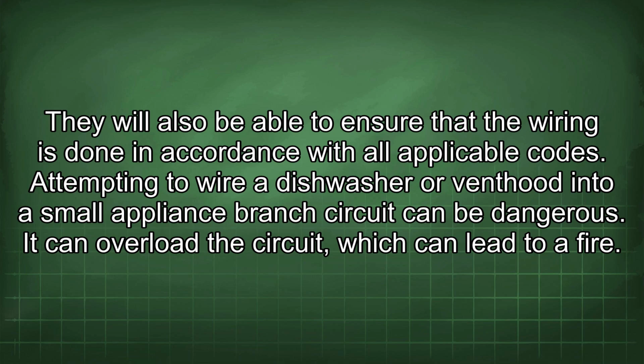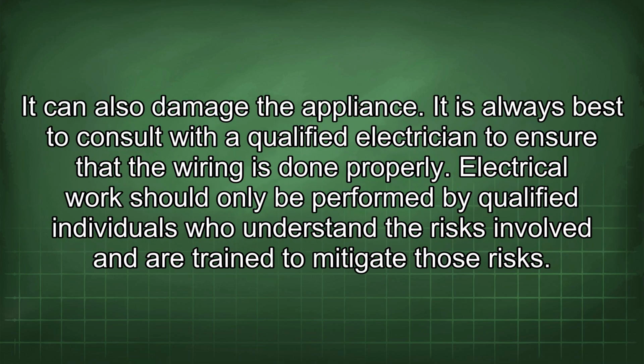Attempting to wire a dishwasher or venthood into a small appliance branch circuit can be dangerous. It can overload the circuit, which can lead to a fire. It can also damage the appliance. It is always best to consult with a qualified electrician to ensure that the wiring is done properly.